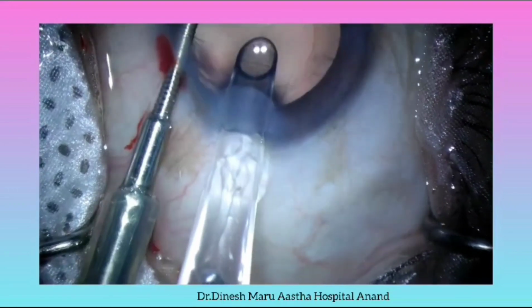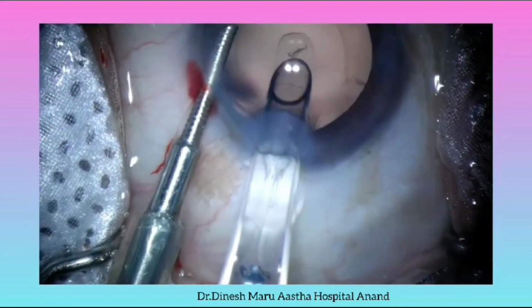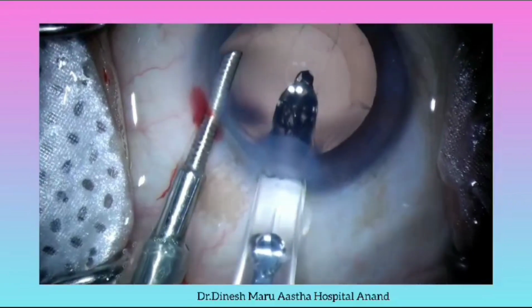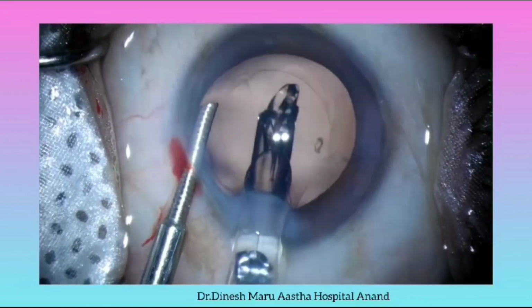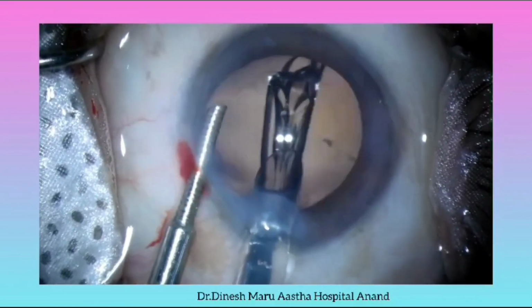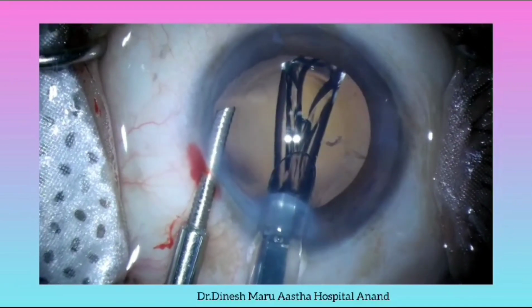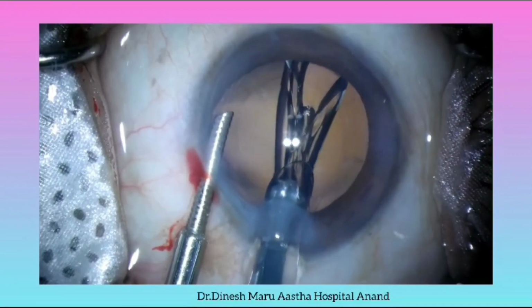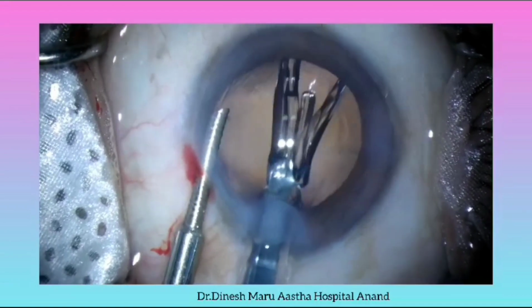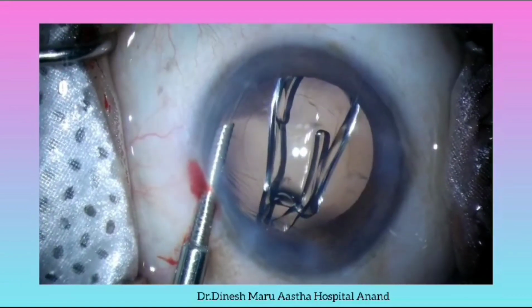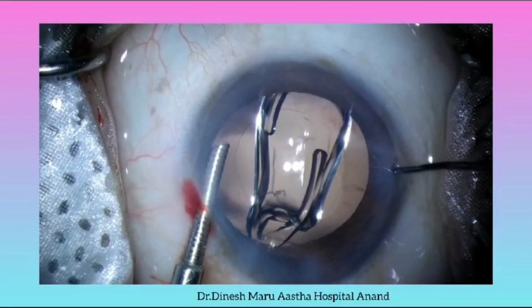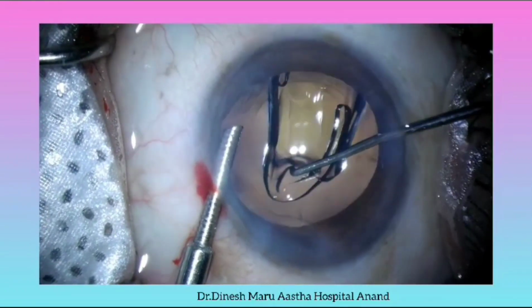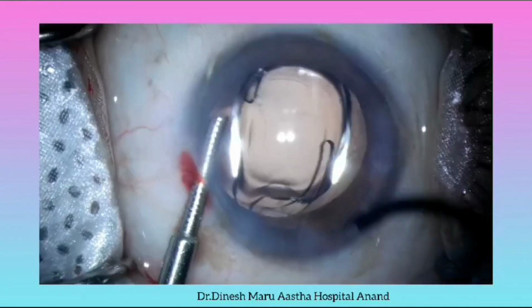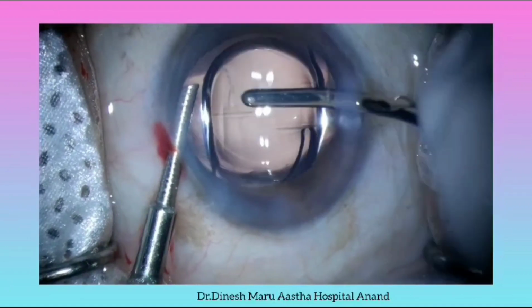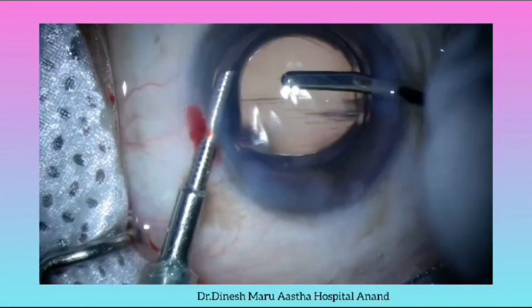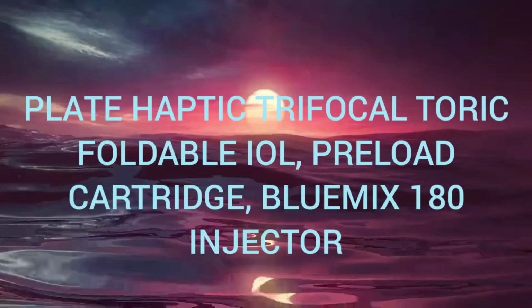It requires two hands for the screw injector to insert the IOL, so hydroimplantation is done only by using an anterior chamber maintainer and thus it is not possible to use an irrigation cannula or phacoemulsification system. With the injector held in one hand, insert the narrow tip of the cartridge through the incision. Use the other hand to initiate the clockwise screwing motion, gradually inserting the IOL into the eye. As the trailing haptic emerges, guide the IOL using the dialer or Y-hook into the bag.